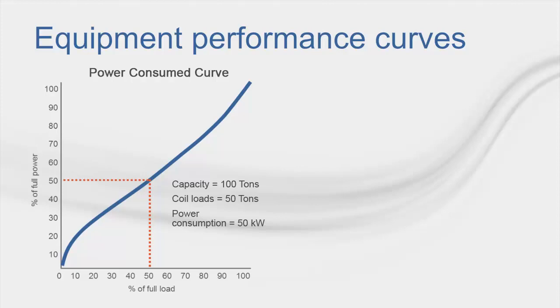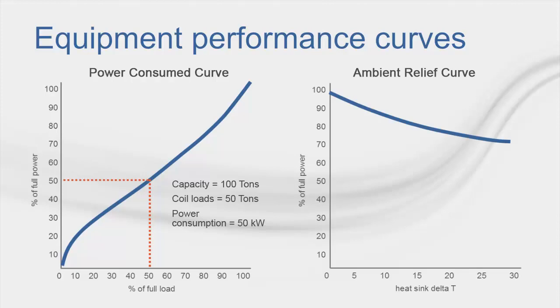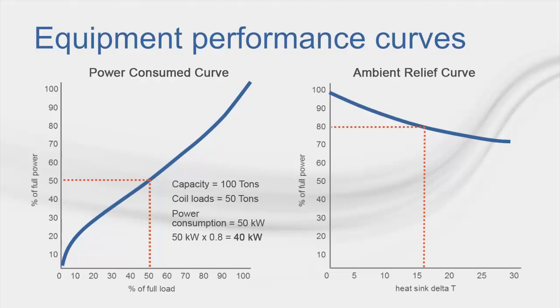By referring to the ambient relief curve and understanding that for the given hour, the condenser entering water or air temperature is 16 degrees Fahrenheit cooler than the design conditions, we can see that this curve would indicate that we would expect a further 20% reduction in energy consumption for the equipment. So, by multiplying the 50 kW by 0.8, we can expect that the energy consumed by the equipment for the given hour is 40 kW.